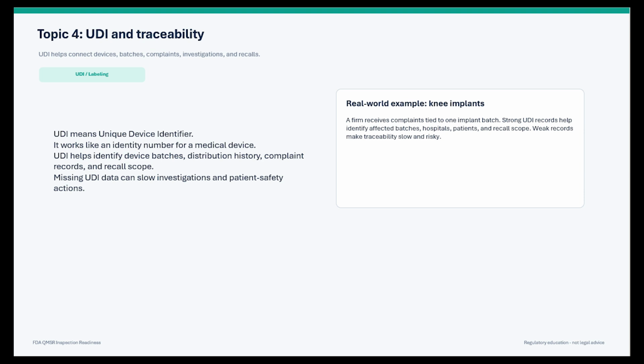UDI means Unique Device Identifier. In simple terms, it works like an identity number for a medical device. UDI helps connect devices, batches, complaint records, investigations, distribution history, and recall scope. When UDI data is complete and connected, the company can move faster during complaint investigations and field actions. When UDI data is missing or disconnected, investigations can slow down and patient safety decisions can become harder.